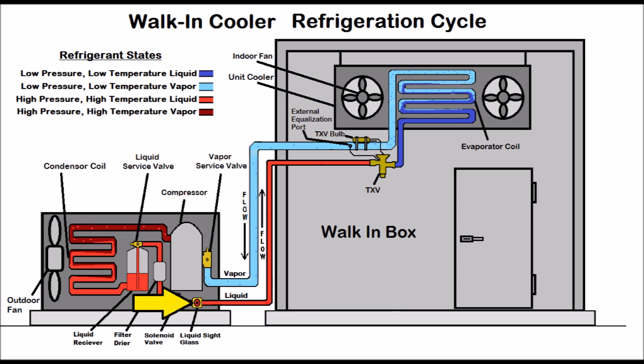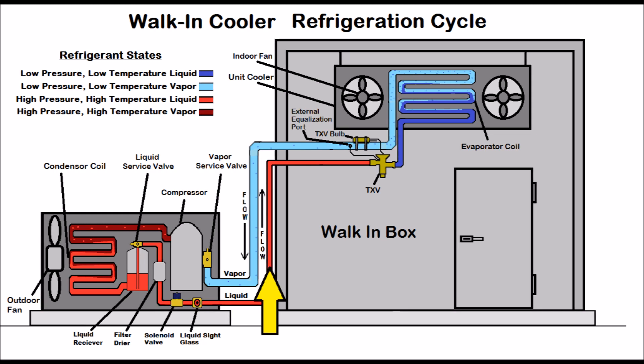Then the refrigerant goes through the liquid sight glass. The liquid sight glass could be in the outdoor unit, but more preferably it's right in front of the thermostatic expansion valve. It's best to have it closer to the TXV. As the sub-cooled liquid heads through the liquid sight glass, if you have a solid column of liquid the sight glass will be clear — unless there's an obstruction like a clogged filter dryer. The sub-cooled liquid then heads into the TXV as a high pressure high temperature sub-cooled liquid refrigerant.